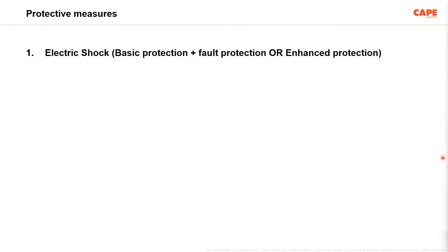These are a little bit technical words, but for electrical engineers, sometimes these are useful to understand. So basic protection alone cannot provide you safety. You need basic protection and fault protection. Now, these basic and fault protective measures are selected based on the environment where you need safety. For example, some of the protective measures such as automatic disconnection of supply, double or reinforced insulation, electrical separation of one item of current using equipment, or extra low voltage.